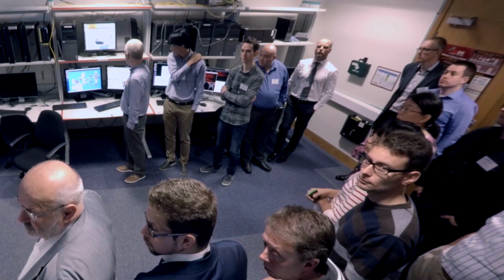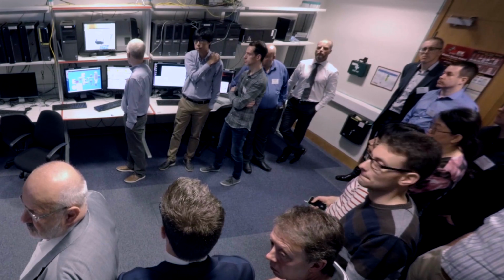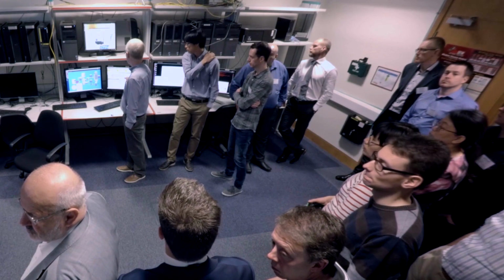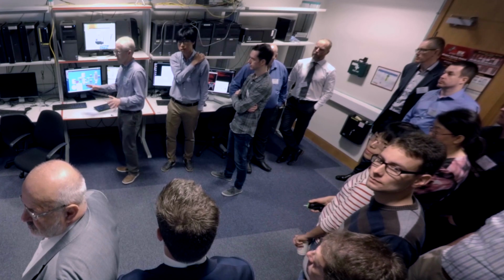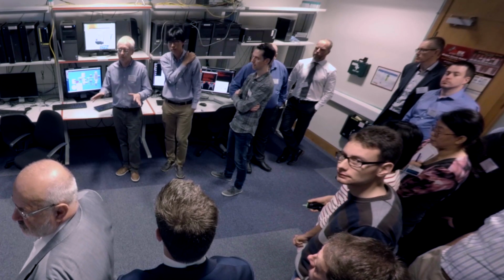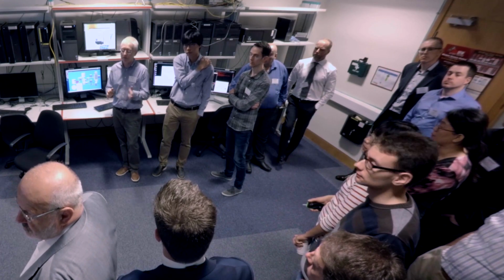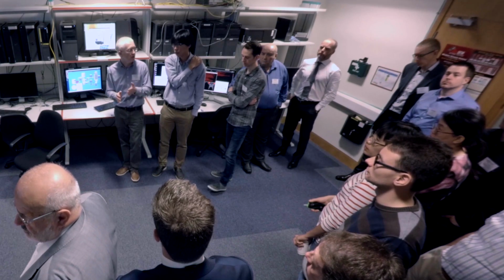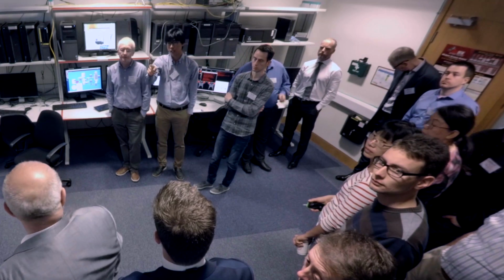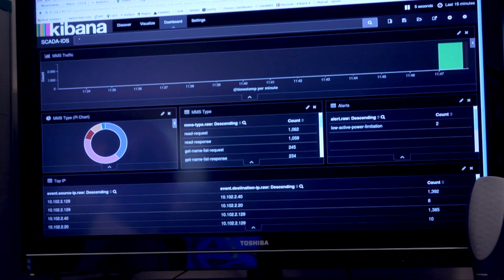So you can see some of the traffic here. It's exercising the 61850 model, the tree of functional level, much more deeply, and basically just doing a tree search and values. Yeah, you can see the surge in the volume of the traffic. That could be the evidence of someone scanning the networks.